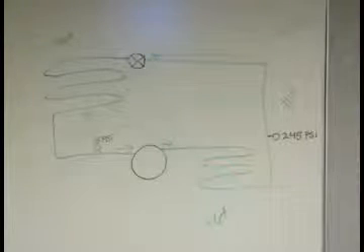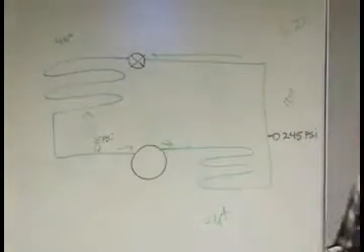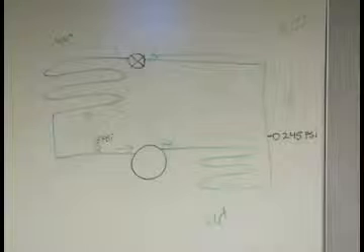Heat pumps, again, there's a lot of different configurations. You can do an air-to-air. Both coils are air coils, which in this part of the country is not a real attractive option. The amount of heat that you're going to absorb on our evaporator, which is now outdoors in the winter, in 20-degree air, is not a lot. It's going to be really difficult to absorb much heat out of that air. So they lose efficiency drastically as the temperature gets colder outside.